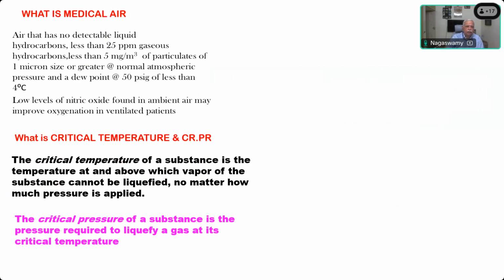So air that has no detectable liquid hydrocarbons, less than 25 parts per million gaseous hydrocarbons, less than 5 milligram per cubic meter of particulates of 1 micron size or greater at normal atmospheric pressure, and a dew point at 50 psi gauge pressure of less than 4 degrees centigrade. And low levels of nitric oxide found in ambient air may improve oxygenation in ventilated patients. So that may be permitted to some extent. But other things, there should be no liquid hydrocarbons, there should be no particulate matter more than 1 micron size. These are the two things which are very important.